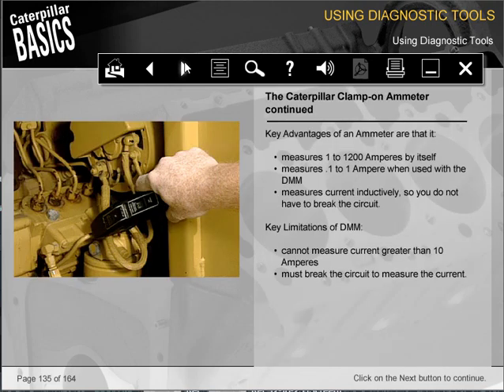Key advantages of an ammeter are that it measures 1 to 1200 amperes by itself, measures 0.1 to 1 ampere when used with a DMM, and measures current inductively, so you don't have to break the circuit. Key limitations of a DMM: it cannot measure current greater than 10 amperes, and you must break the circuit to measure the current.